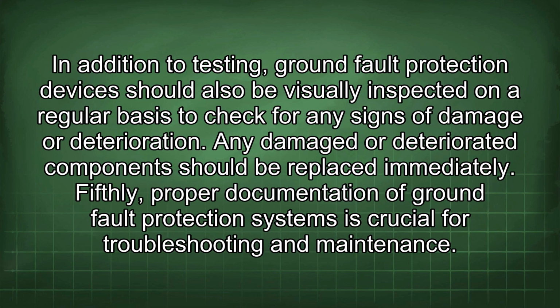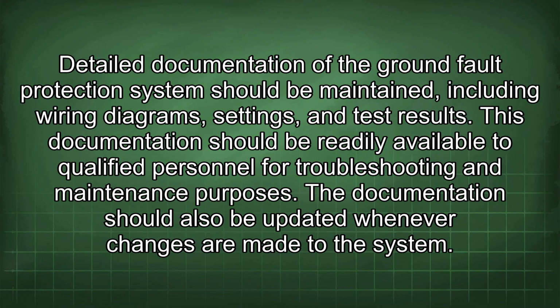In addition to testing, ground fault protection devices should also be visually inspected on a regular basis to check for any signs of damage or deterioration. Any damaged or deteriorated components should be replaced immediately. Fifthly, proper documentation of ground fault protection systems is crucial for troubleshooting and maintenance. Detailed documentation of the ground fault protection system should be maintained, including wiring diagrams, settings, and test results. This documentation should be readily available to qualified personnel for troubleshooting and maintenance purposes. The documentation should also be updated whenever changes are made to the system.